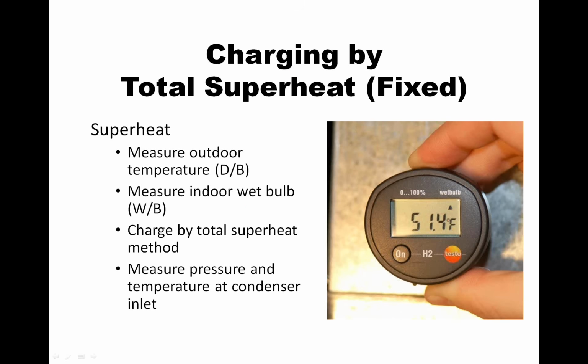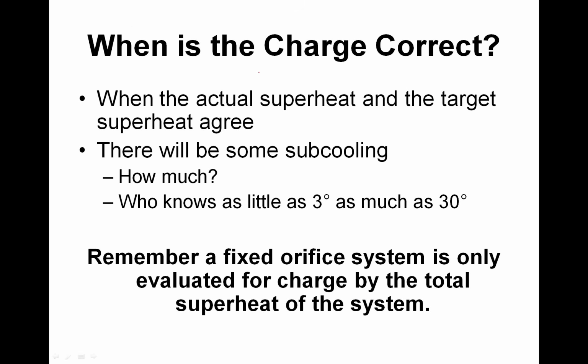Now this is a wet bulb thermometer. It's an older Testo 605-H2, but this is the type of tool we're going to use to measure return air wet bulb temperature. All right, so when is the charge correct? Well, when the actual superheat and the target superheat agree, the charge is correct.